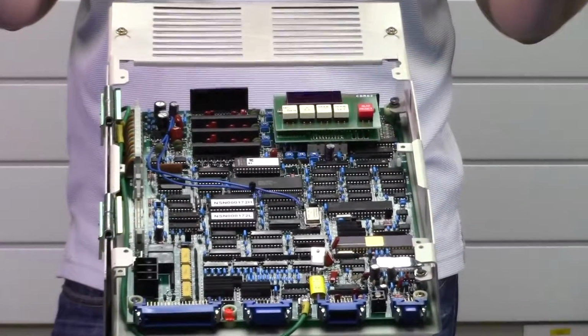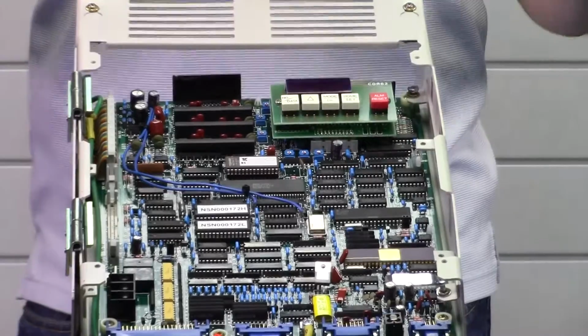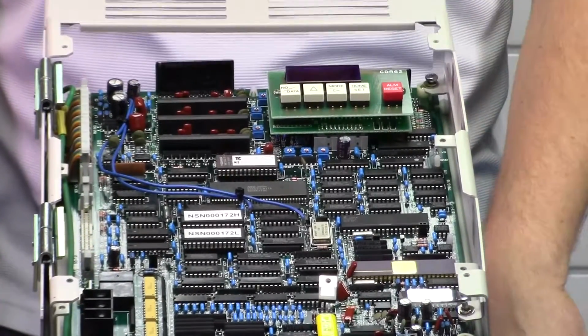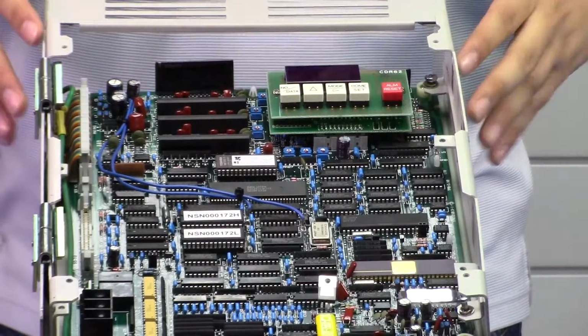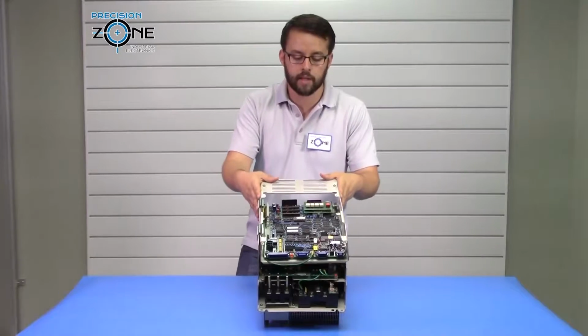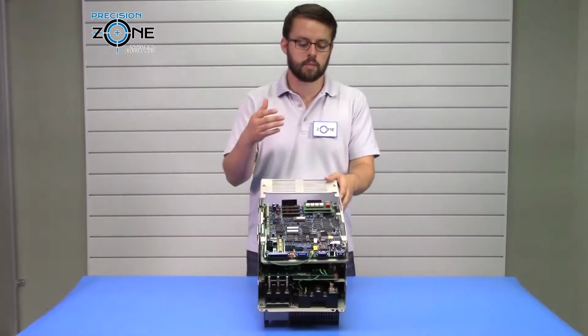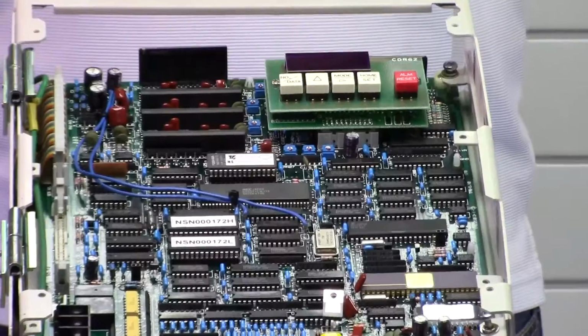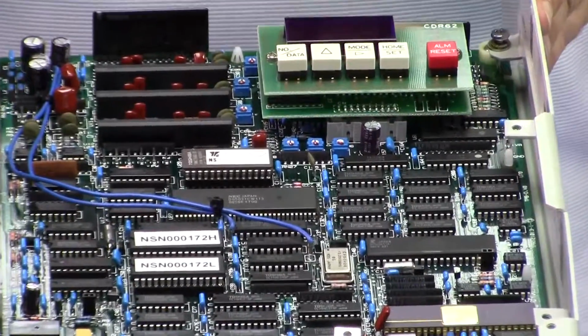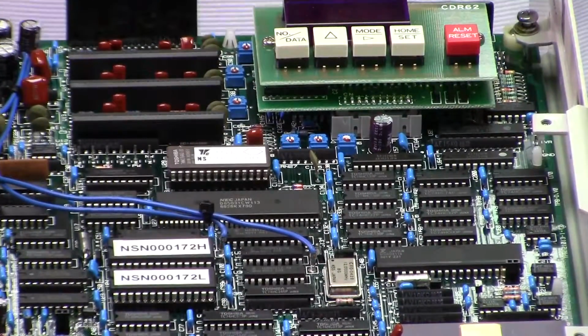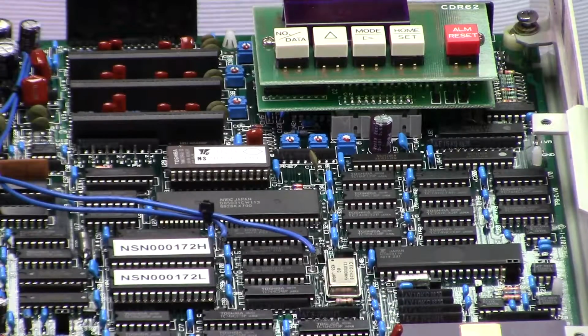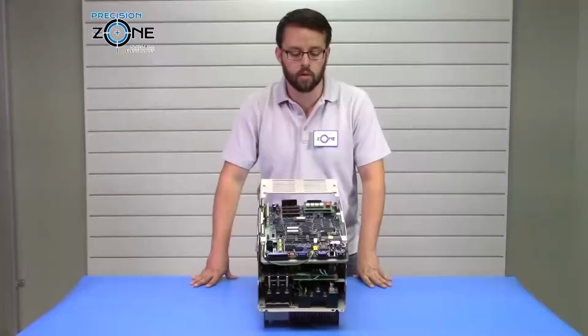If you're getting overspeed or deviation alarms, OS or DEV, those could be related to parameter settings in the drive. They can also be related to a PG connection or your motor connection. So you want to verify that your connections are set up properly, that your cables are in good condition. It's possible it could be a PG issue as well.